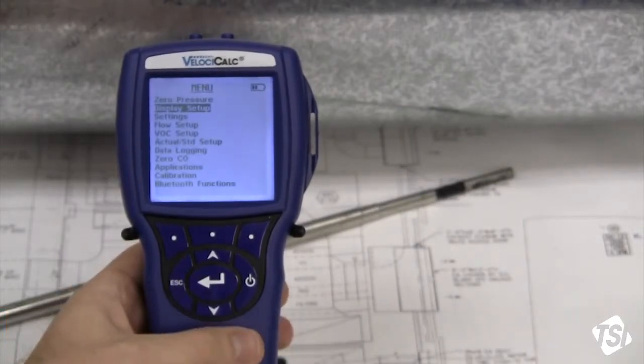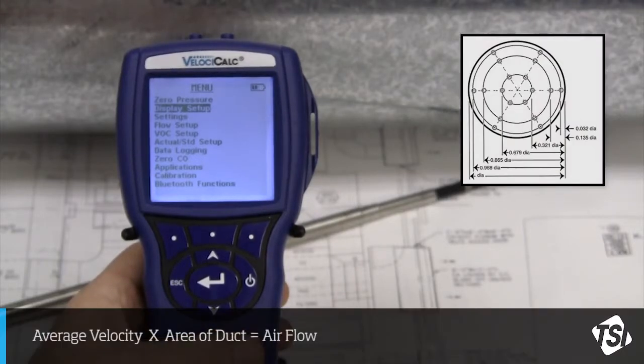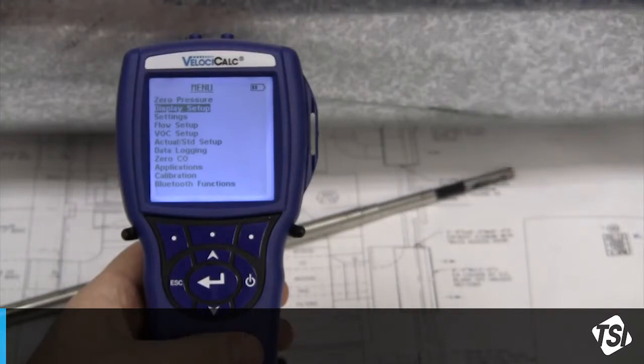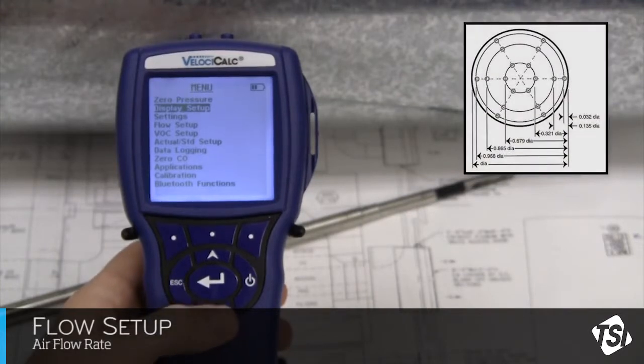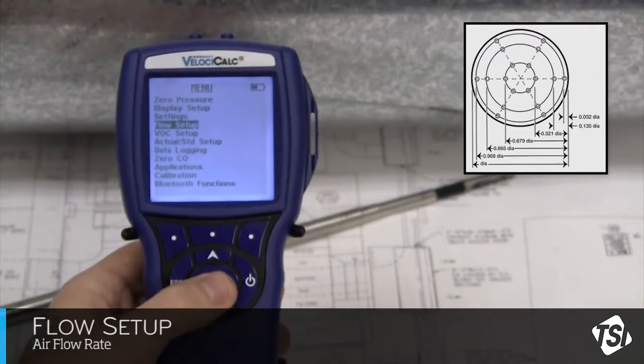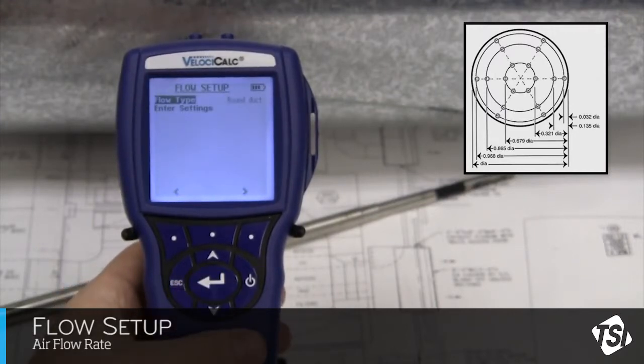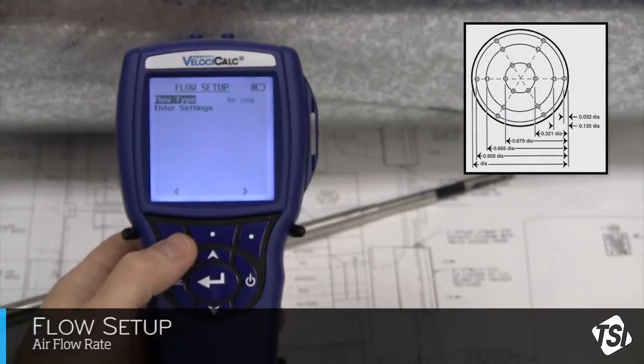Now we need to set the correct dimensions for my duct into the VelociCalc. Remember, airflow is calculated by multiplying velocity and the square footage of the area being measured. While back in the main menu, arrow down to Flow Setup. Press the Enter button. Use the right or left soft key to scroll through the duct options. You have the option to select round duct, rectangular duct, or if you already know the square footage of the duct, you can use duct area. There are other options as well.